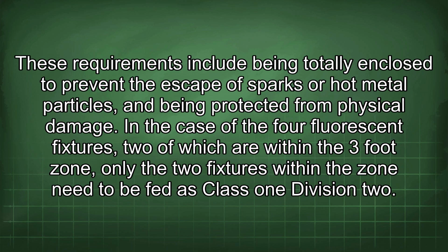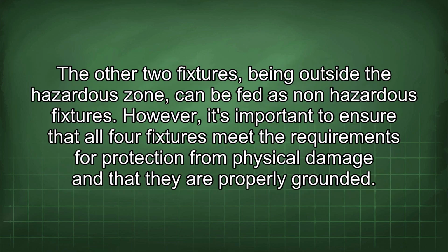These requirements include being totally enclosed to prevent the escape of sparks or hot metal particles and being protected from physical damage. In the case of the 4 fluorescent fixtures, 2 of which are within the 3-foot zone, only the 2 fixtures within the zone need to be fed as Class 1 Division 2. The other 2 fixtures, being outside the hazardous zone, can be fed as non-hazardous fixtures. However, it's important to ensure that all 4 fixtures meet the requirements for protection from physical damage and that they are properly grounded.